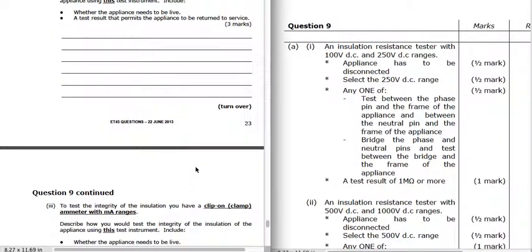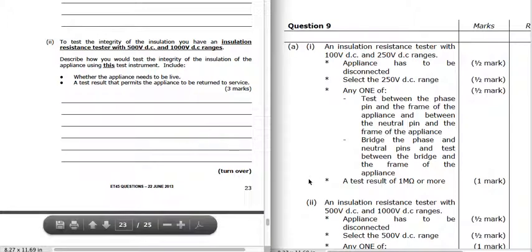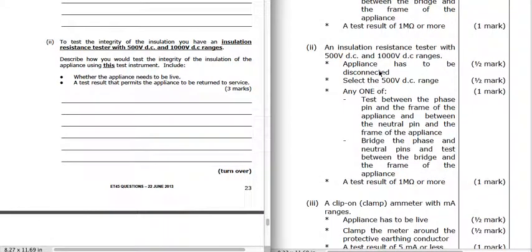For the same appliance but with an insulation resistance tester that only has 500-volt DC and 1000-volt DC ranges: disconnect the appliance and go for the 500-volt DC setting. Test between each conductor and earth, or bridge the phase and neutral together and test to earth for the appliance. We're looking for a test result of 1 megaohm or more.